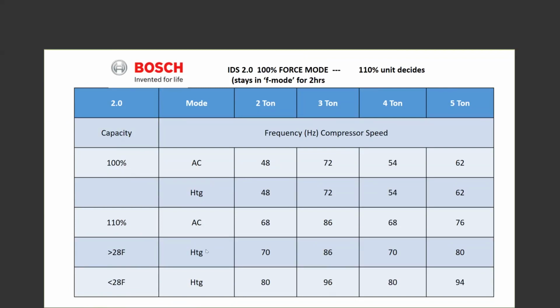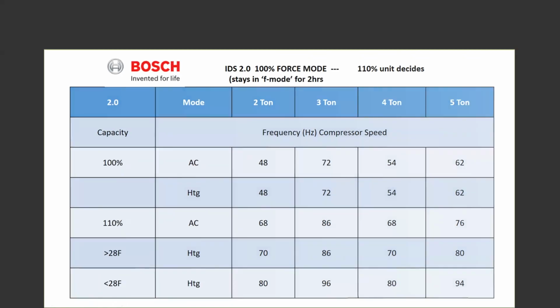It's staying right here. Nothing wrong with the board. I would bet you that somebody pushed in the J2 button. Maybe they don't work for you anymore. And you've got a 2-ton unit. No big deal. Turn the power off, flip the J2, turn the power back on, wait 5.5 minutes, allow it to come back on, and you're probably going to see 72 as a 100% button at that time.